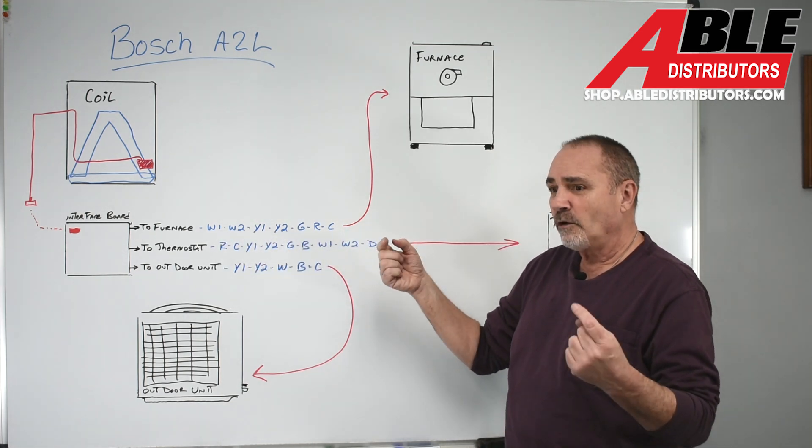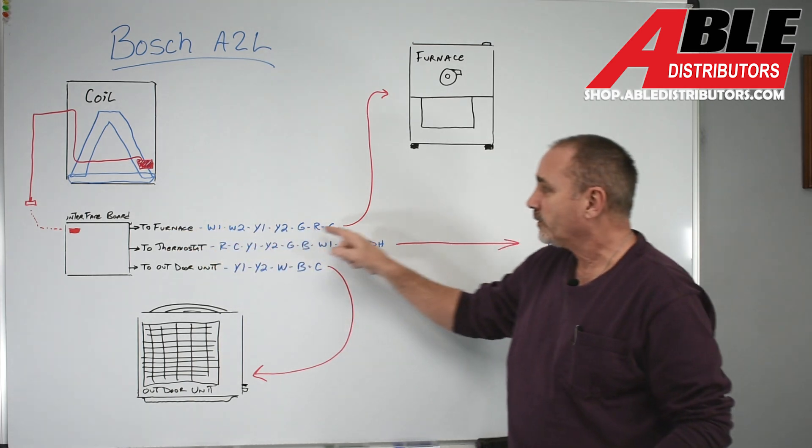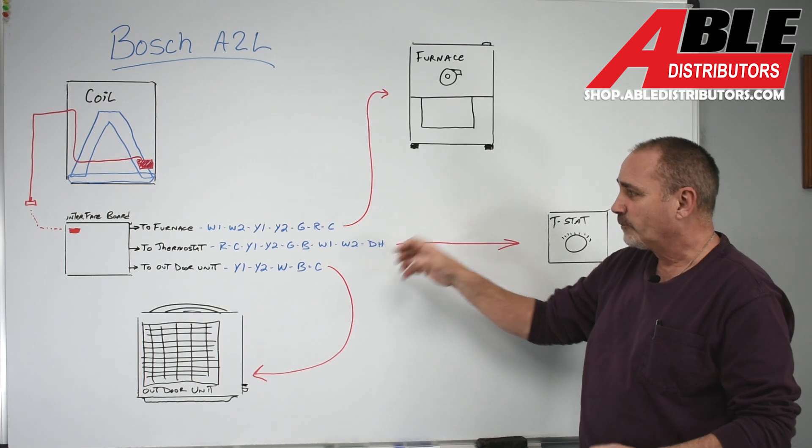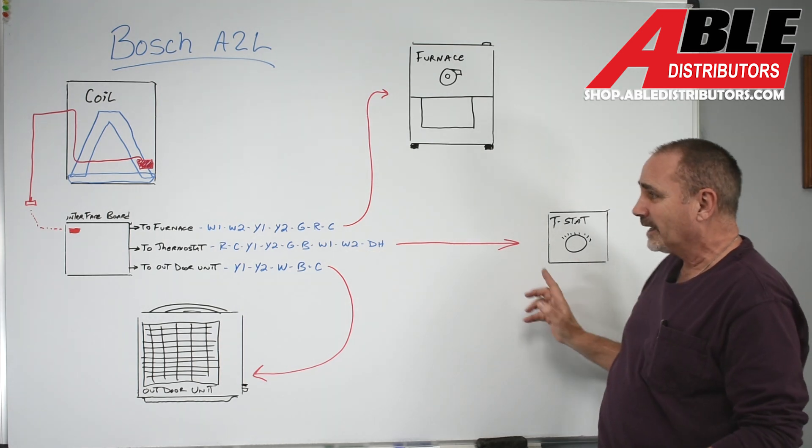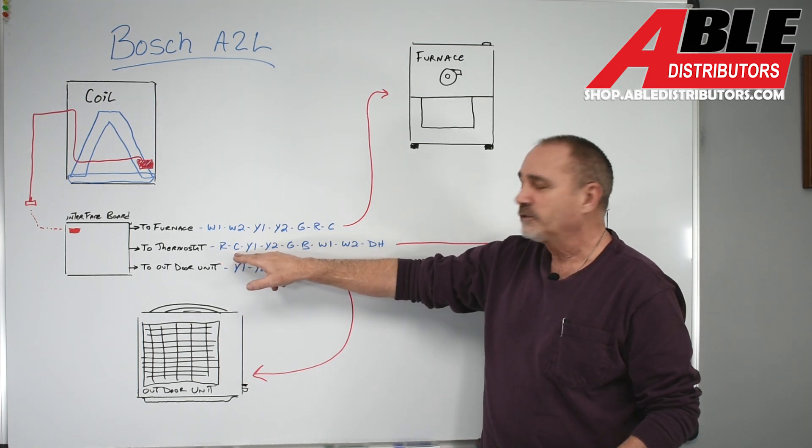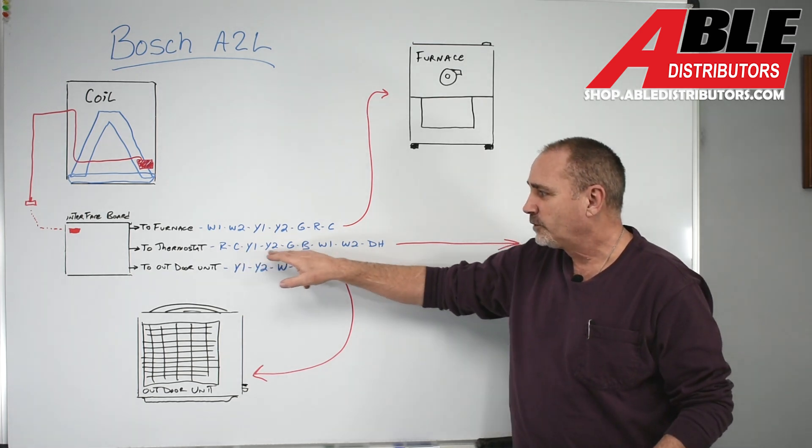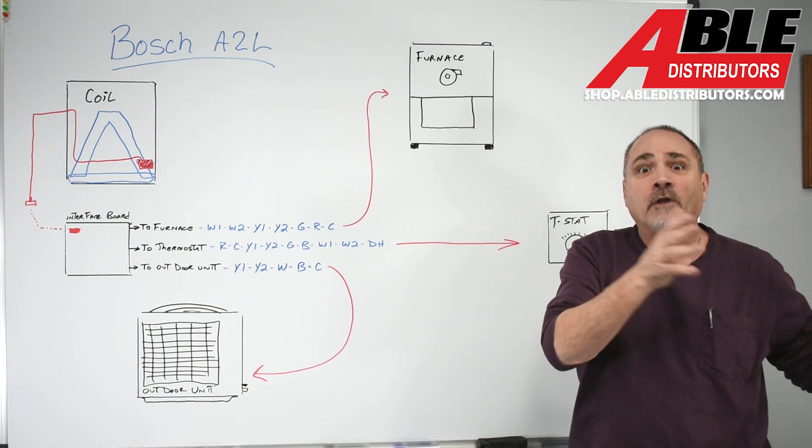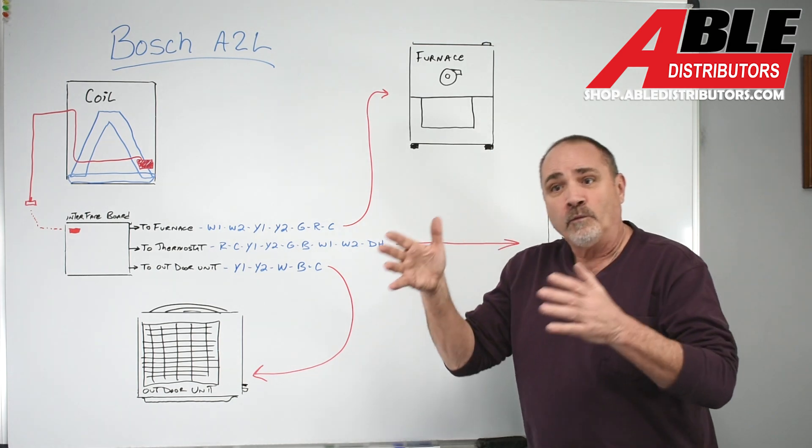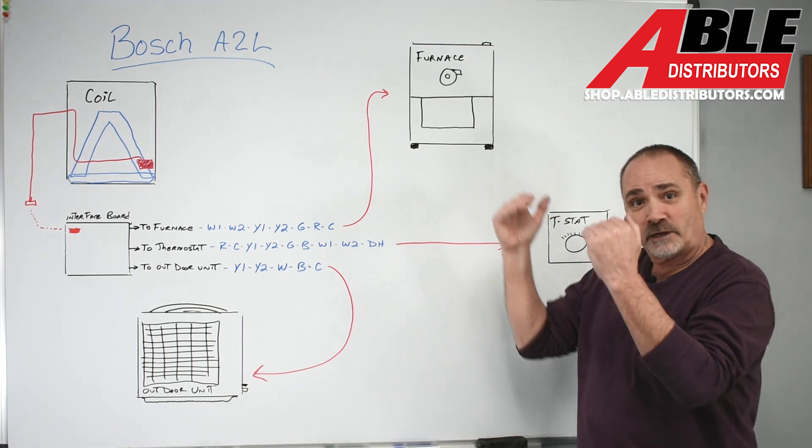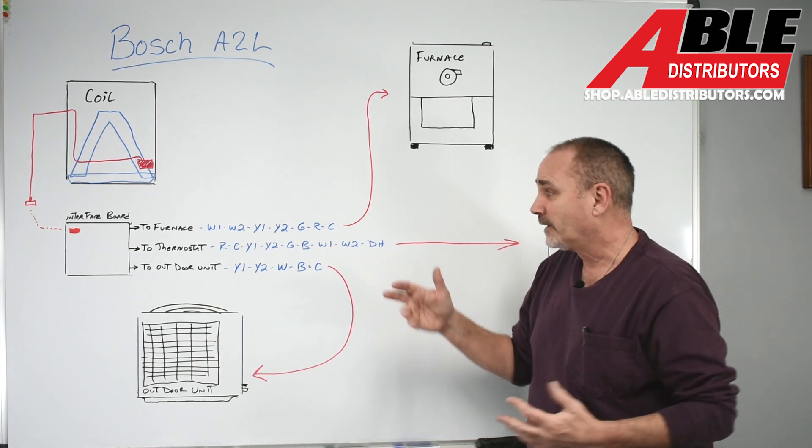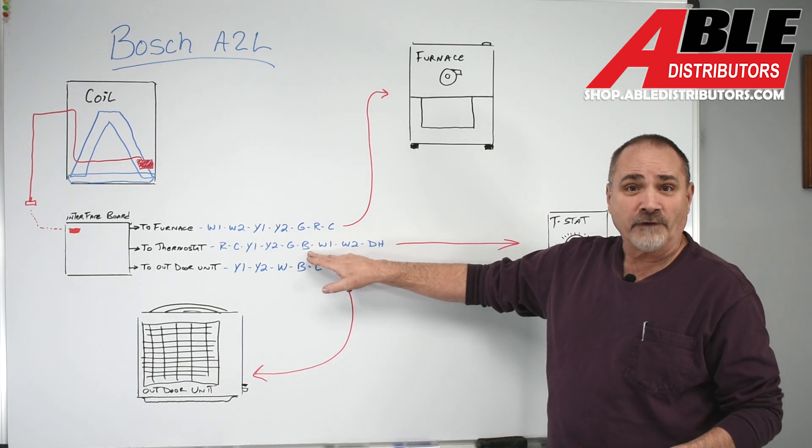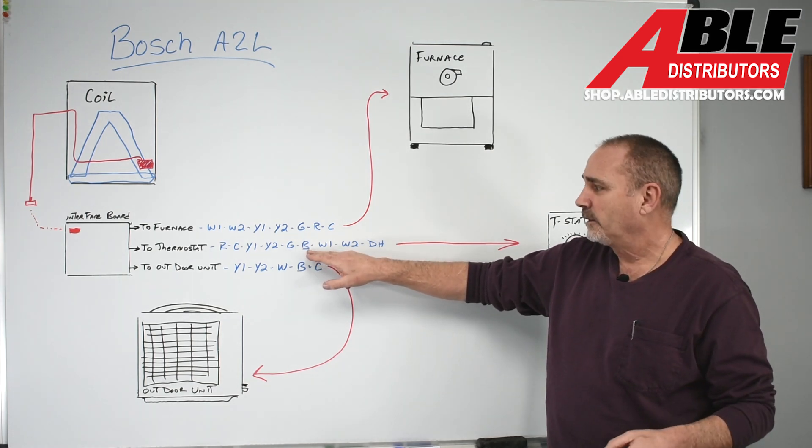There is no intermingling of the wires. One group of wires goes to the furnace. Forgive my drawing. One group of wires, and they're separate, goes to the thermostat. Again, the thermostat, you're going to use R. You're going to use common if you've got a Wi-Fi thermostat. You're going to choose whether you've got a Y1, Y2 thermostat. Again, the Bosch will move along with you. So whether you want the two stage and the Bosch will modulate and follow behind or not, that's up to you. Green, you're going to need that. Blue, or your reversing valve, again on Bosch, that's on heat. You're going to need that.